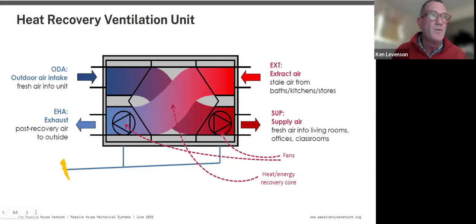A key thing with the mechanical system, specifically ventilation, is that if the ventilation unit is within the conditioned space of the home, the ducts going to the outside are exterior, so that unit is essentially exterior. The air, once it comes out of the heat exchange, is interior, but we need control of this. We want this unit to be as close to the exterior as possible. If the unit's outside, this is also outside. There are losses associated with the ducts to the outside, and we want to minimize those runs. This is a more consequential aspect in terms of potential damages if it's not installed properly.